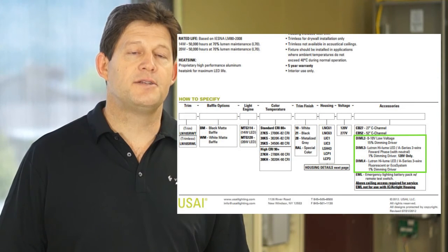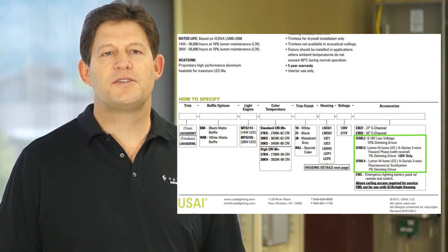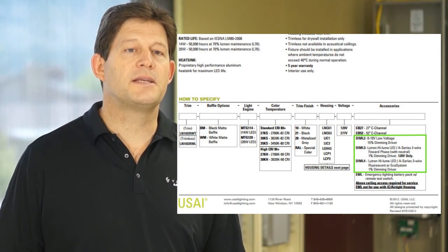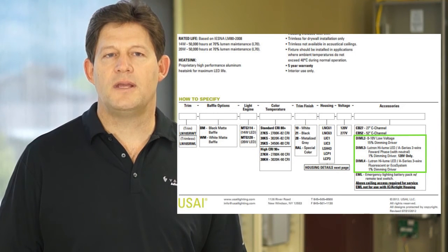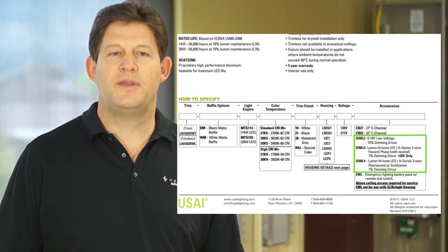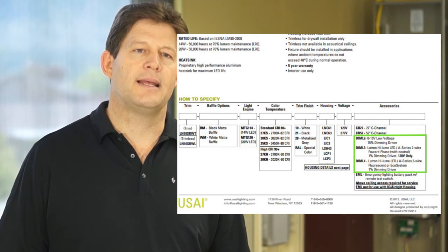If the dimming technology is already specified, it's simply a matter of selecting the appropriate dimmer. If you have specification influence, you can make some value judgments. In this case, the 0 to 10-volt dimmer has a dimming floor of 15% versus 1% with the other two, so I would rule that option out immediately.